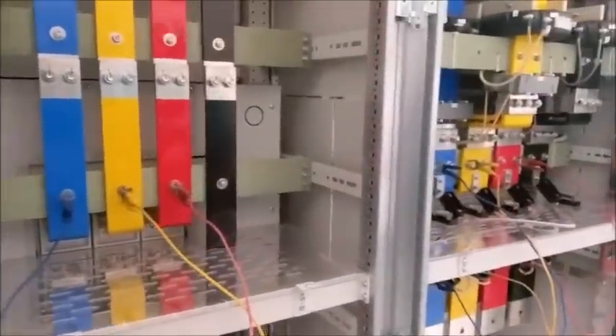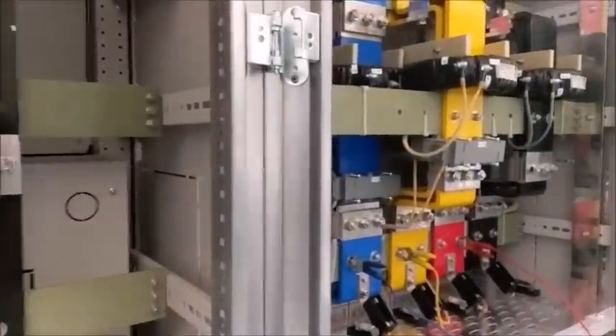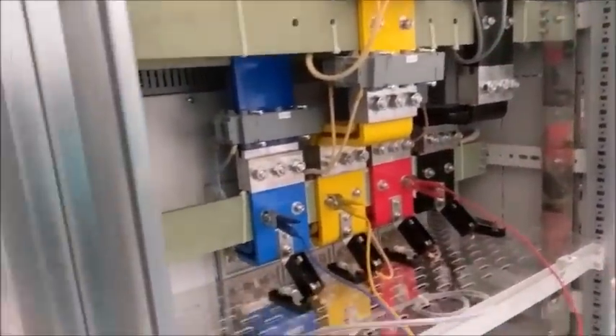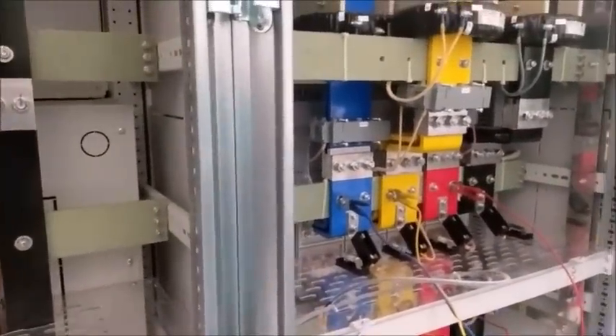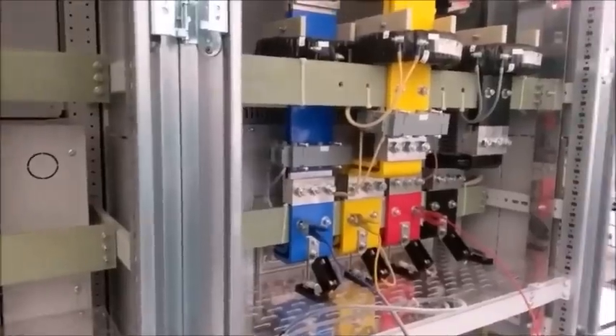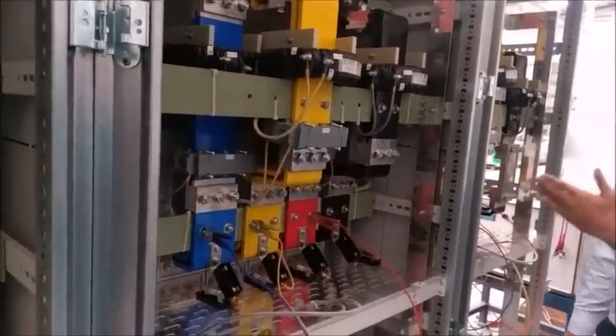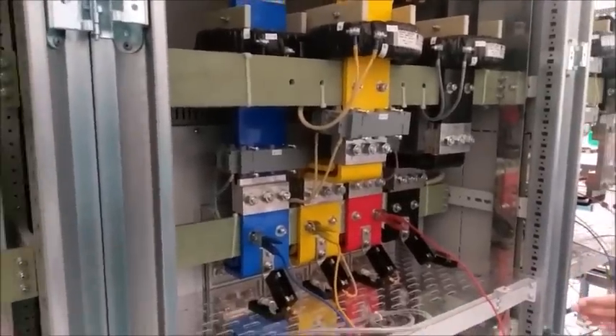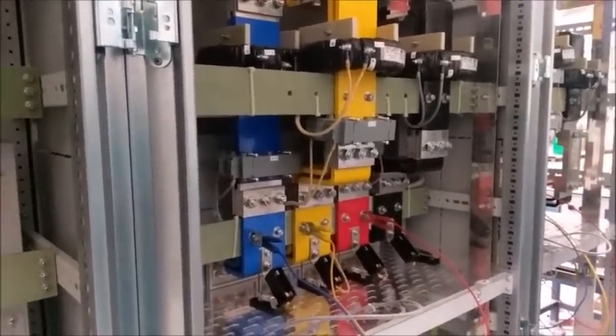Where is the main breaker? The main breaker is here. There are actually two main breakers, so there is a mechanical interlock and an electrical interlock. If this breaker is on, the other will not get on. If this is on, it will not get on.